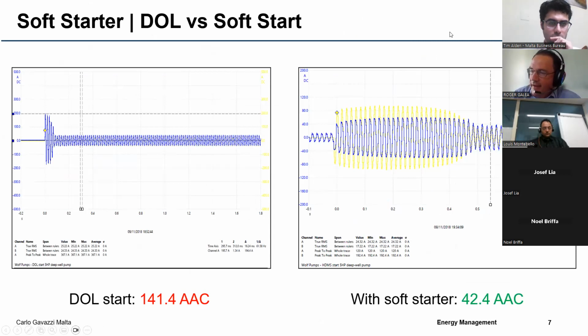Important to say that such new high efficiency motors, however, tend to have what we call a higher inrush current, okay? So this graph is showing the nominal current that a motor usually takes, and this is the initial current when you are starting it direct online. One of the measures we have taken, because we changed the motors to high efficiency motors, is to more and more deploy the soft starters we have in our portfolio, which help basically to achieve this type of transformation.